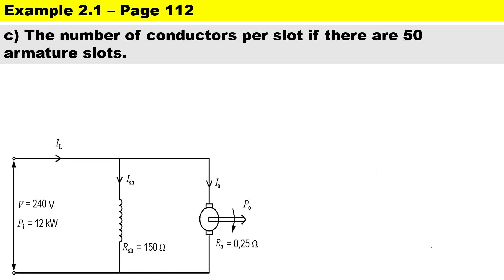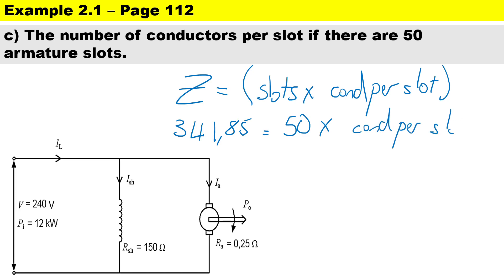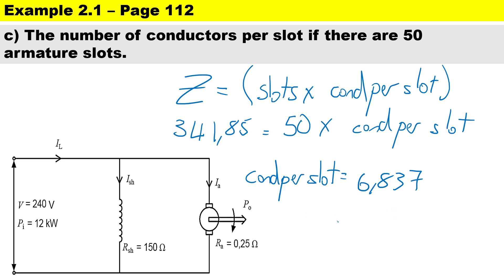The final question asks for the number of conductors per slot if there are 50 slots. The relationship is: Z = number of slots × conductors per slot. Substituting Z = 341.85 and 50 slots gives 341.85 / 50 = 6.837. Since you cannot have a fraction of a conductor, we round up to 7 conductors per slot.